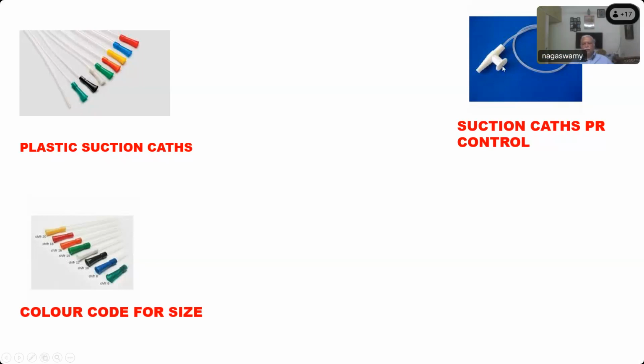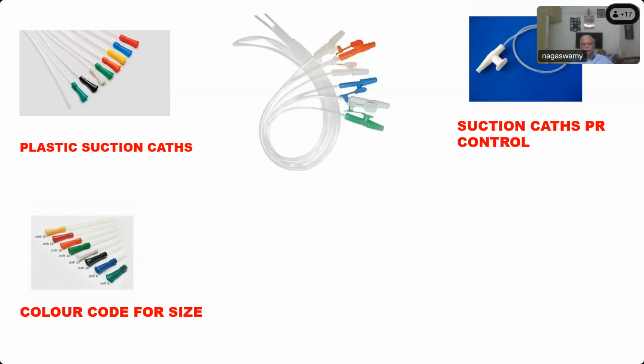So when you introduce it, especially into a tracheal tube, you should not introduce it with the suction on. To prevent any collapse of the airway, first you lubricate and introduce the tube up to the length where you want to remove the secretion. Then occlude this port, and then you suck out the secretion. Then again during removal, you have to take your finger off so that there is no continuous suction while removing. Otherwise, it will cause collapse of the lung. So to prevent that, you can control the pressure by occluding this. So this is a suction catheter with pressure control. And these are the various sizes and color codes of that same thing. And what is this?